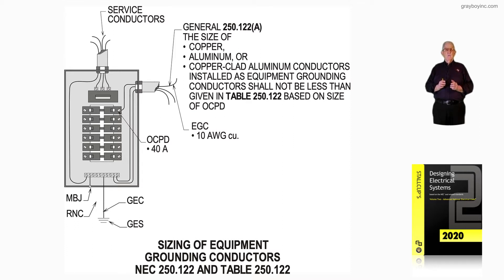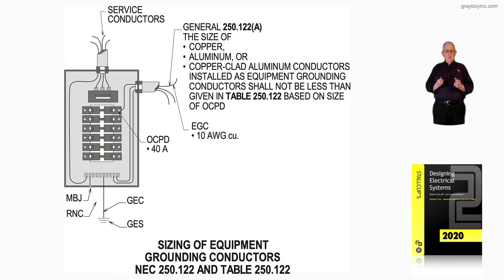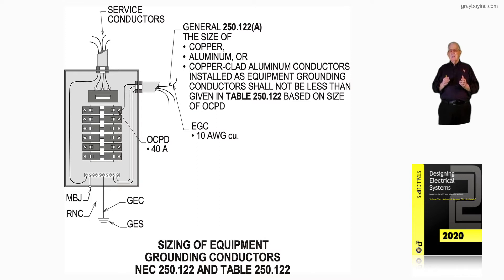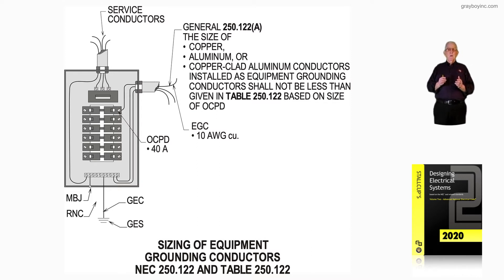The call-out talks about the general rules of sizing equipment grounding conductors, 250.122A. The size of the conductor — it could be copper, aluminum, or copper-clad aluminum conductors installed as equipment grounding conductors — shall not be less than given in Table 250.122, based upon the overcurrent protection device.